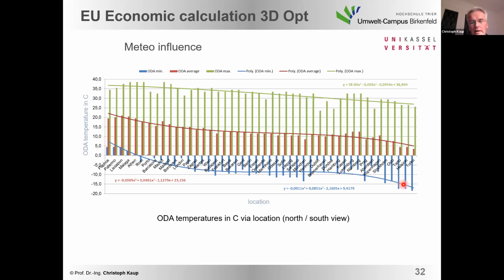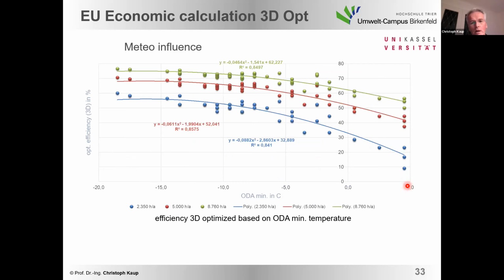And it makes sense to take it because the outdoor air temperature is also a given temperature. Summer temperature is not always given by the manufacturer. So that's the reason why we took the winter temperature. And you see here a clear link between the optimums we found and the temperature for the several operation modes.